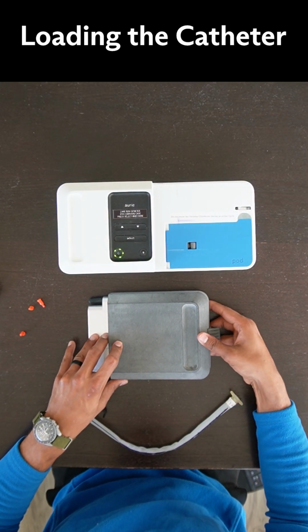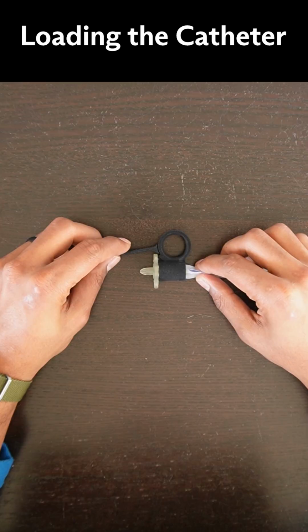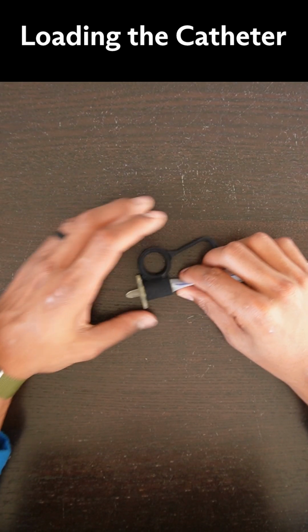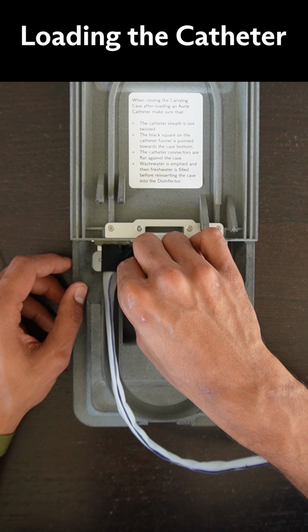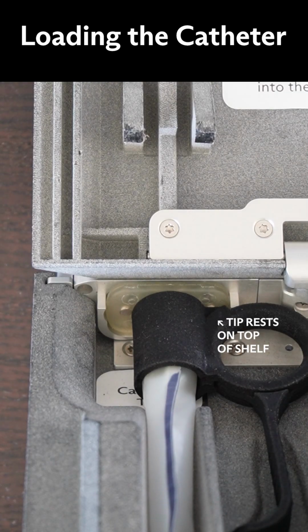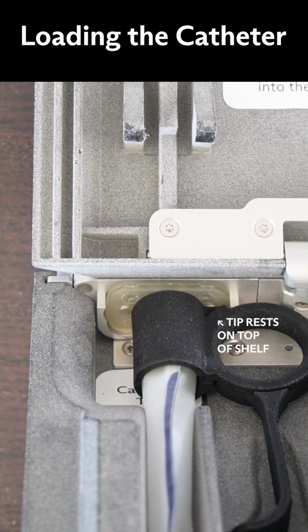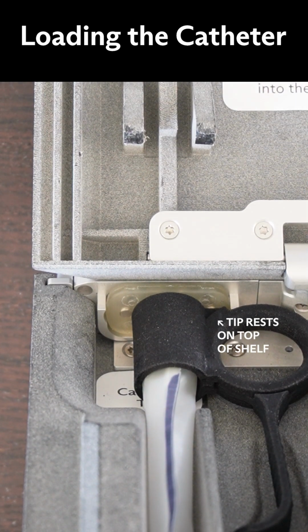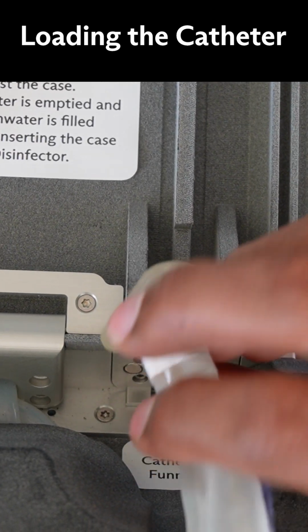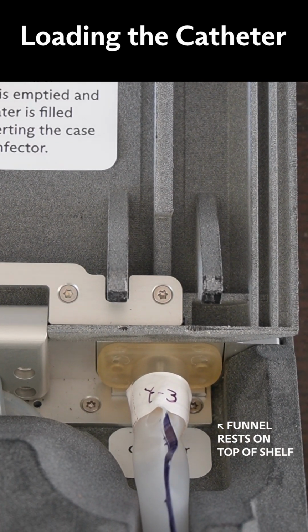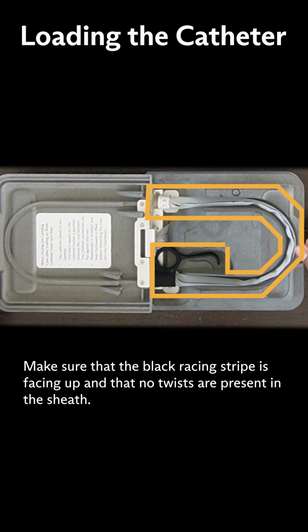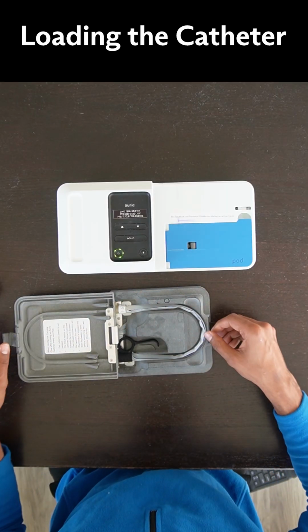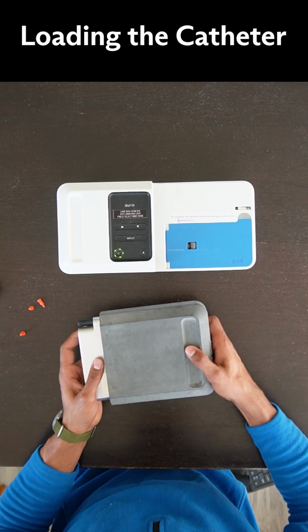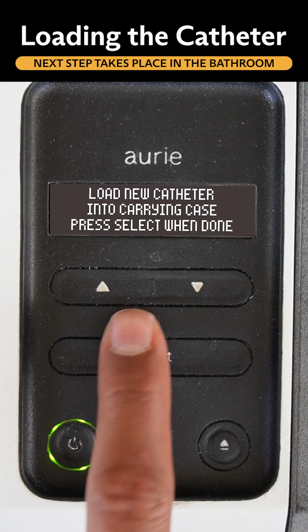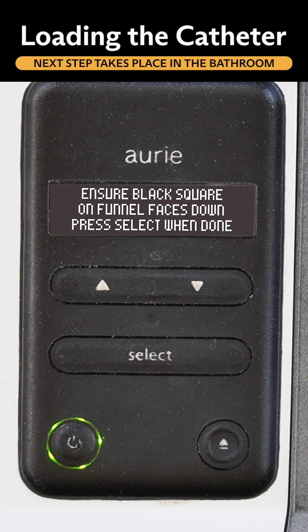Open the case by opening the latch at the non-aluminum end of the case. Next, take your catheter and make sure that the handle is stowed for storage. Insert the introducer tip into the case with the stowed handle to the right, place the catheter onto the aluminum shelf in the case. Next, insert the funnel end into the case where the label indicates, with the black square pointing down onto the aluminum shelf in the case. Check the catheter sheath for any twists in the sheath. Close the case and relatch it. Press select on the Aurie user interface to advance the screen to the next set of instructions.